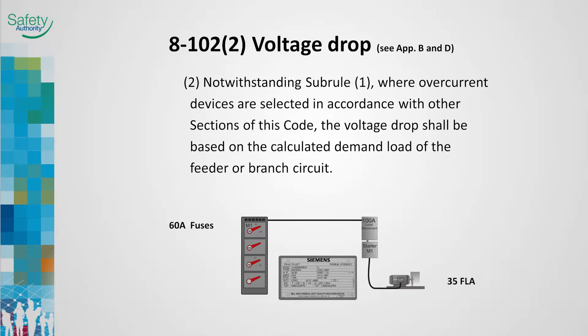Rule 8-102, Subrule 2 allows for some equipment such as motors to have starting characteristics where the overcurrent devices are intentionally oversized to allow for start-up. Rule 28-200, Branched Circuit Overcurrent Protection of Motors, is one such rule. Using the rating of an oversized overcurrent device in your voltage drop calculation would result in circuit conductors unnecessarily too large.